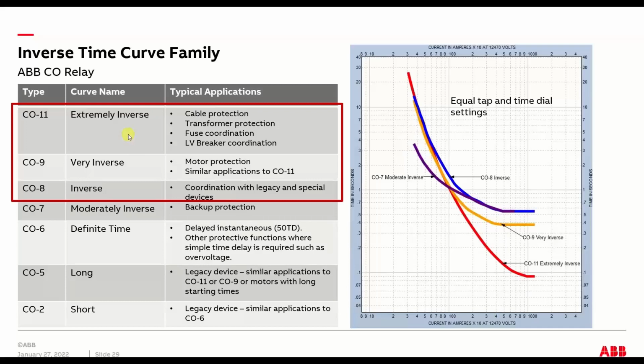Now there are some standardized versions of it. So there's an ANSI standard inverse and extremely inverse. But there's also the CO inverse and the IAC inverse, and those are different. And probably in modern days, you really only have to worry about CO11 through CO8, extremely inverse through inverse. The rest of them, except for definite time, the long and the short and moderately, are kind of legacy curves.